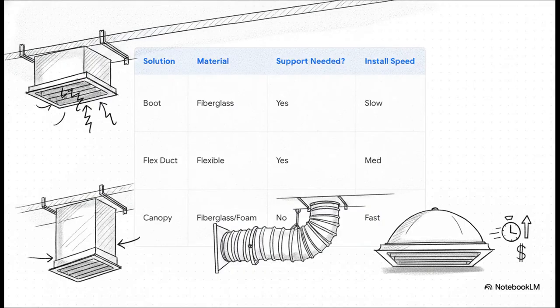So how do HVAC pros stop noise from sneaking in or out of the return air grill in this giant open space? Well, you've generally got three standard solutions. The first is the return air boot. It's essentially an elbow made of fiberglass ductboard. It definitely works, but it needs a solid attachment to the structure. It can't just rest on the grill, which makes it a bit slow to install.